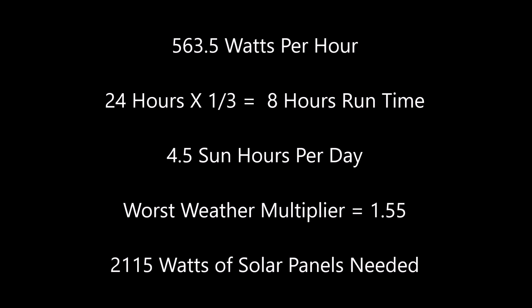There is a multiplier we need to apply to account for clouds passing over the solar panels. This is a worst-case scenario — chances are if you've got bright sunshine every day this won't be necessary — but we have to make sure the system is going to run no matter what. So we're going to use a 1.55 multiplier in our calculations.